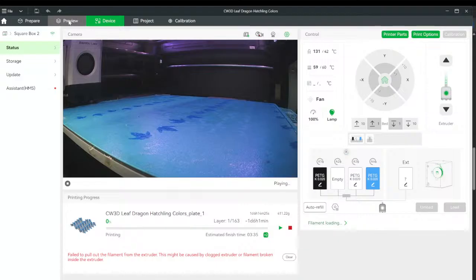We just took apart the AMS HT, which is supposed to be the color it's swapping to, because it's supposed to go from that blue color there to the translucent, and it's not. We took that apart to see if there's anything stuck in the AMS HT. There's not anything in the PTFE tube. And then my only other possible theory is that the Hall sensor could be going bad.